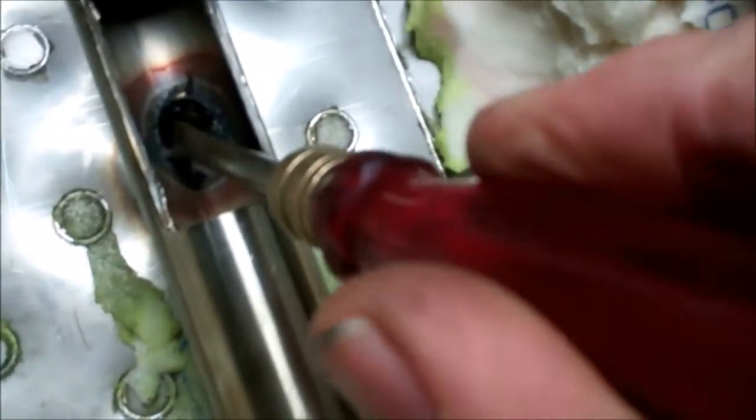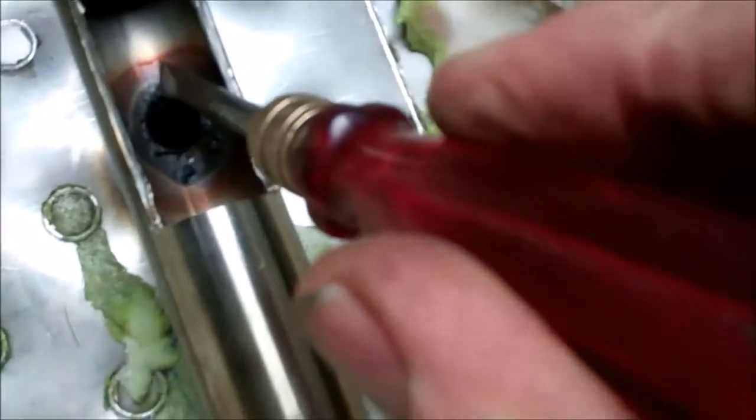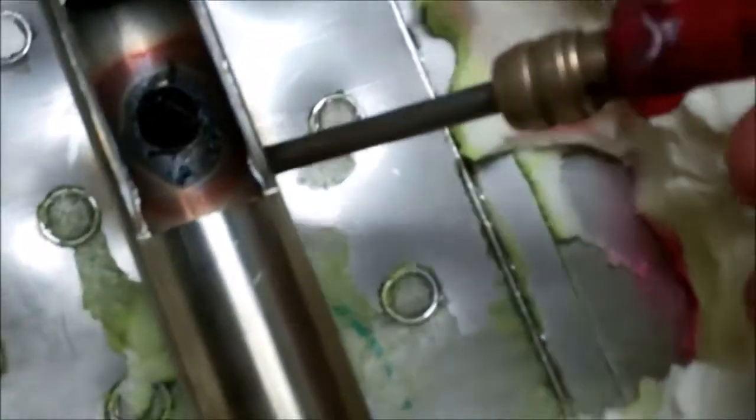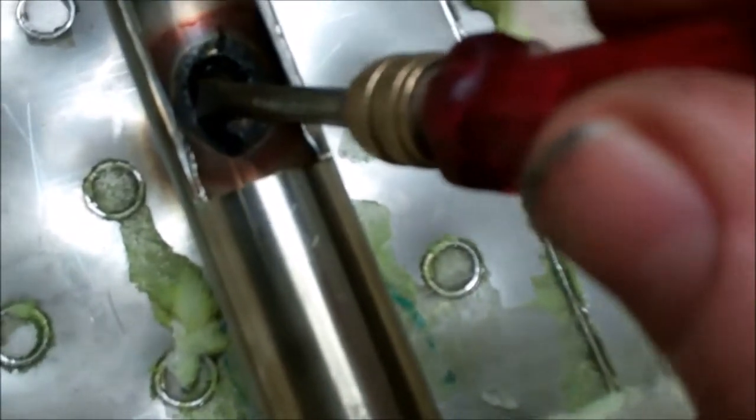The first job is to grind this weld penetration away. This is the penetration that's come through the pipe from the weld on the top there. So I've got to grind that away. It's all oxidized penetration. And then I shall have to put some fluorescent tracing dye to find out where the crack is.